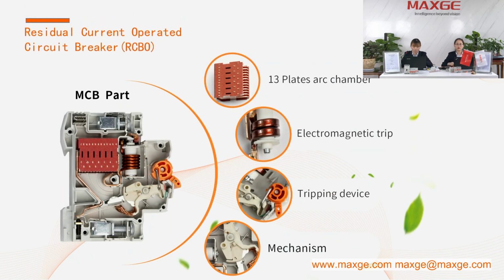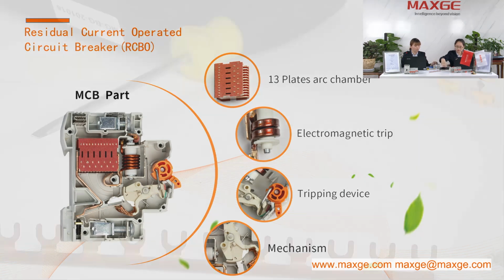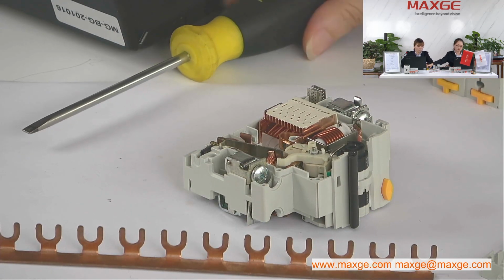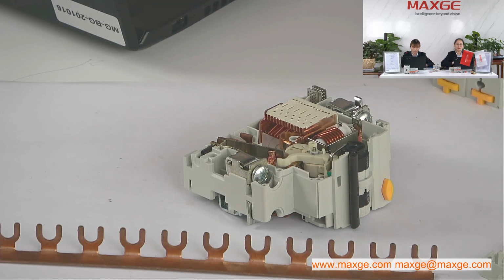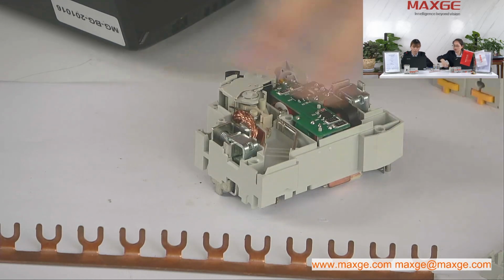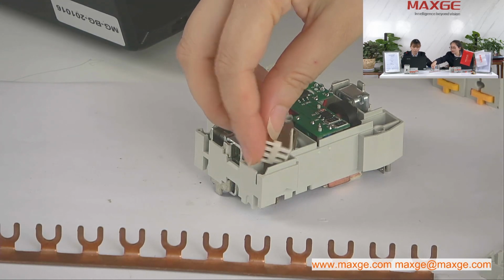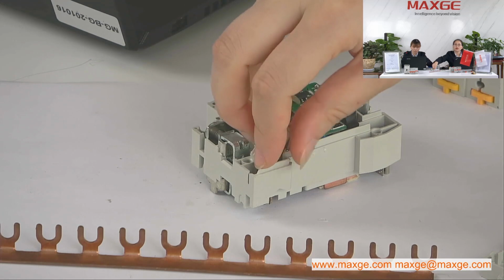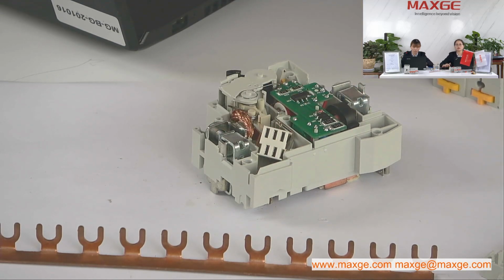Now let me open one RCBO for your further learning. Here is the MCB part. We have an arc chamber with 13 plates, electromagnetic assembling part, handle tripping device, and the mechanical system, and so on. And the RCCB part here, we also have the arc chamber, electromagnetic tripping mechanism, moving contact, and the PCB and transformer part. The arc chamber inside the RCCB part is specially added in this new RCBO.